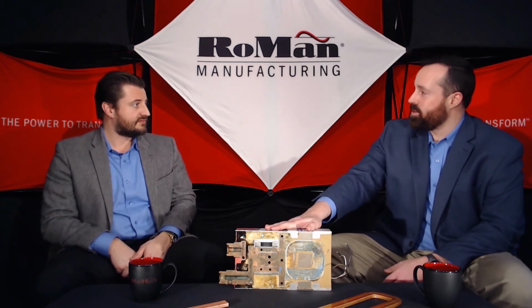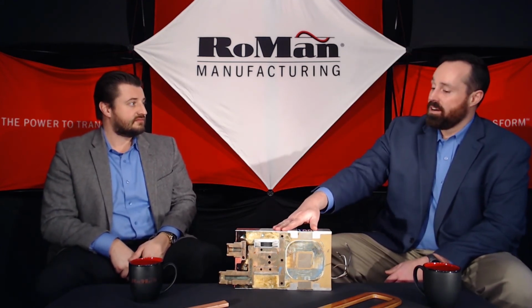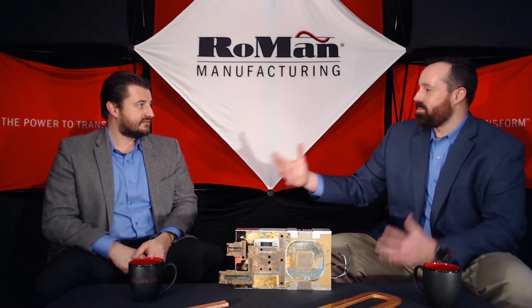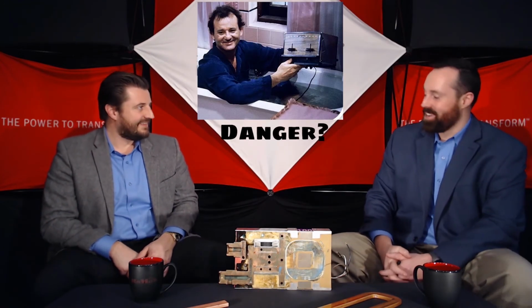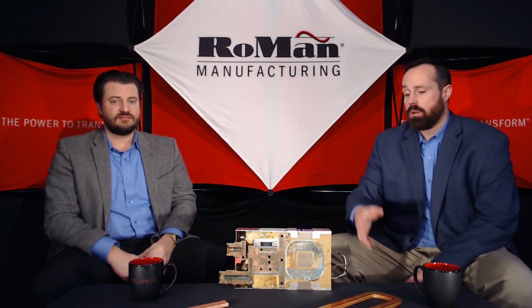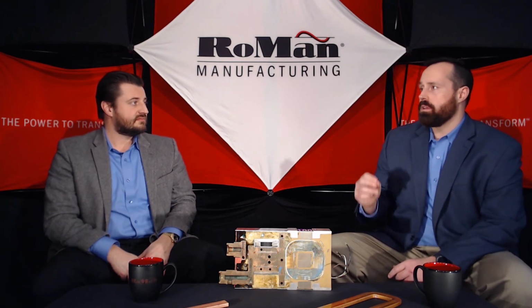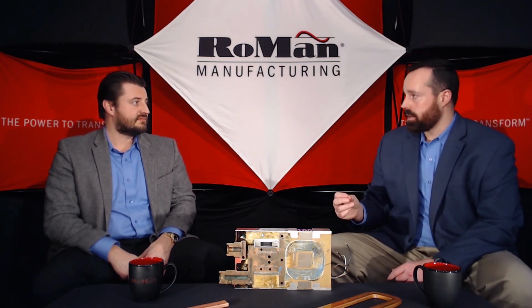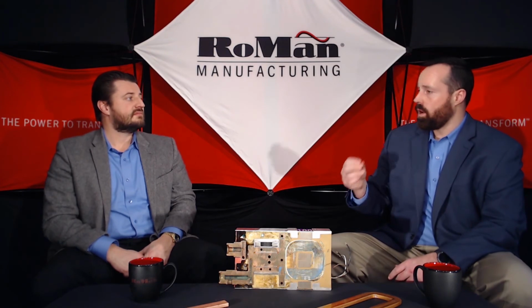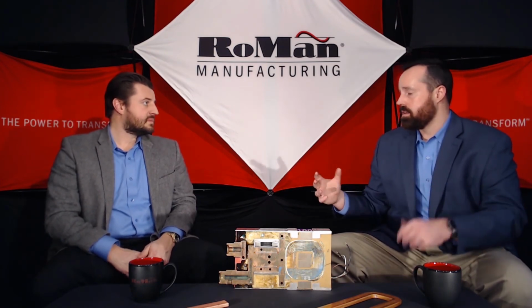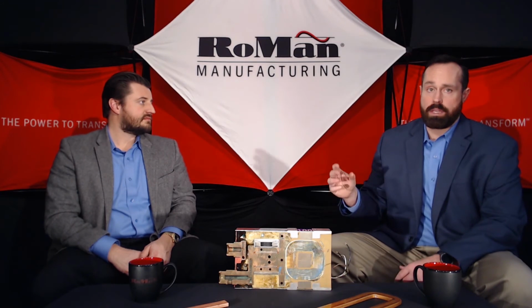Hey, that's a great question. You always see the classic picture of a guy holding a toaster over a bathtub, and this sounds like Groundhog Day. It does. So that's a great question we get all the time. How are we pumping water directly through our secondary and it's not dangerous? The simple answer is that water actually acts as a dielectric in these conditions. Water has great insulating properties, and when you have your transformer properly connected and grounded, it virtually poses no risk if used properly.